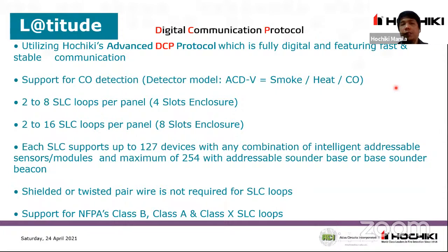So in terms of capacity, we have 4-slot enclosure and the 8-slot enclosure. 4-slot is minimum of 2 loops and maximum of 8 loops or signaling line circuit. So kapag sa 8-slot enclosure naman, minimum of 2 loops and maximum of 16 loops. So in terms of devices per loop, our maximum is 100 up to 127 devices, which is combination of the addressable sensors and modules. So meron tayong allotted for the addressable sounder base, which is 128 to 254. Yun yung allotment natin for addressable sounder base.